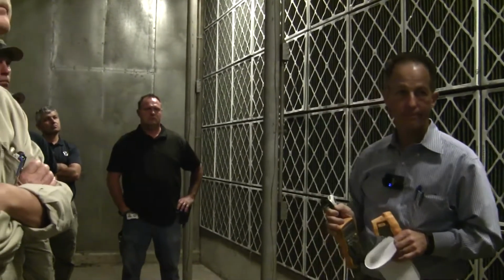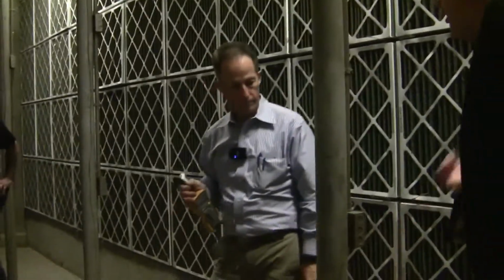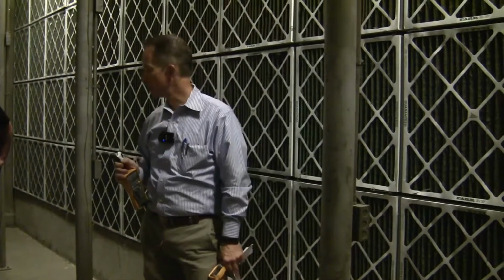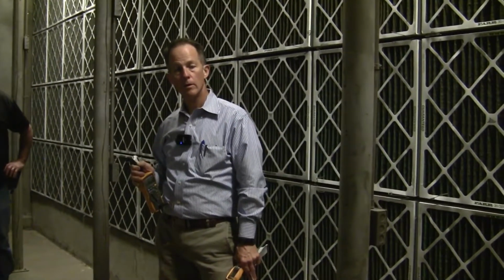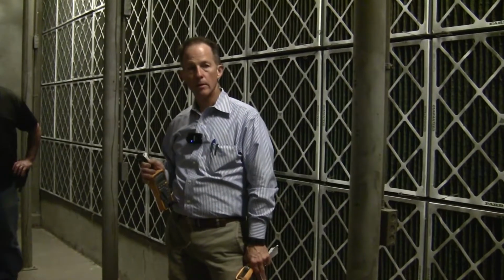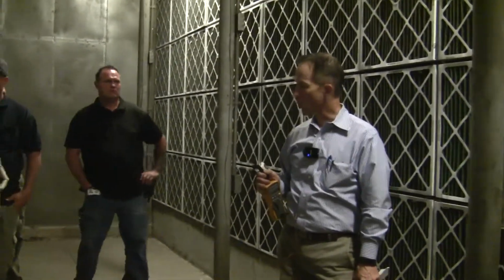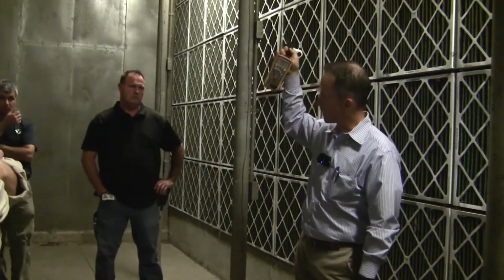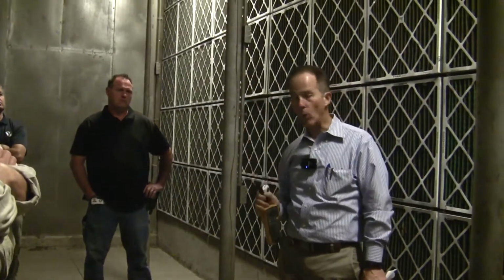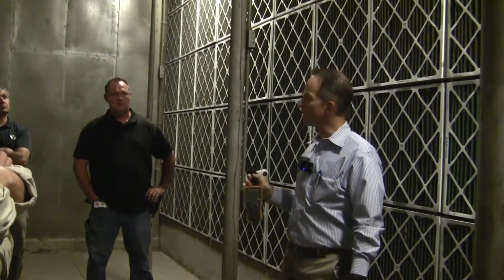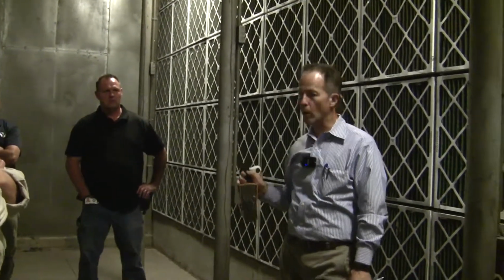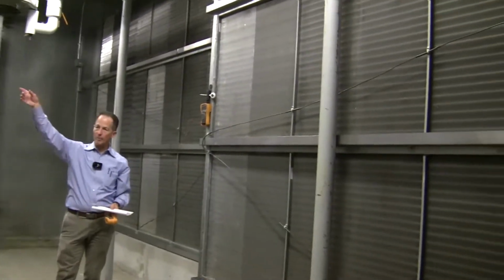Okay. And then just real quick, something else to check on these sometimes, especially if they come through the air handler, if it's a negative pressure, and this is not sealed coming through, then you're pulling air from the outside of the air handler down the tube, and it's hitting the sensor and giving it a false reading. So you have to look in there and maybe put some silicone or something to seal that off. I've seen that a lot. Yeah, you'll see that in rooms sometimes where a positive pressure will push cold air or hot air from up above down the wall into a stat, and it's always reading incorrectly because of it, especially on outside walls.